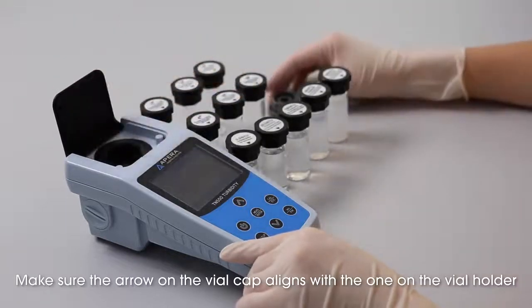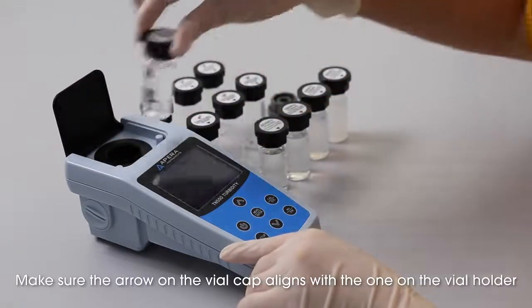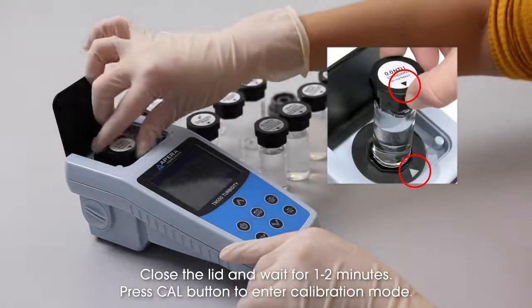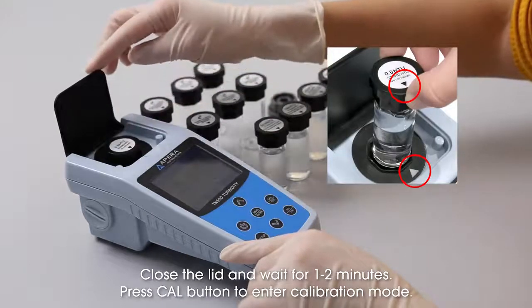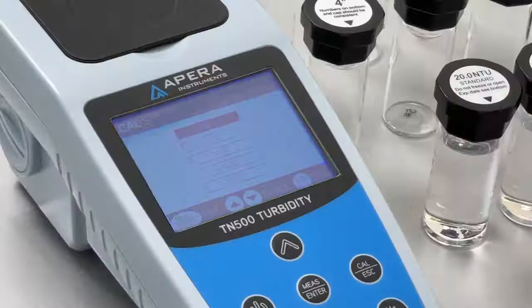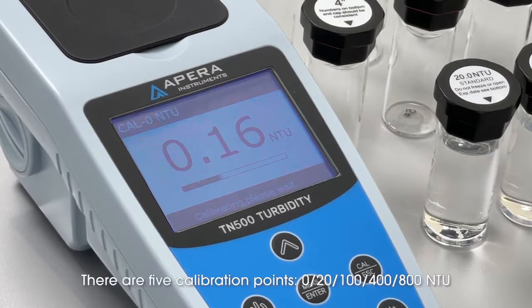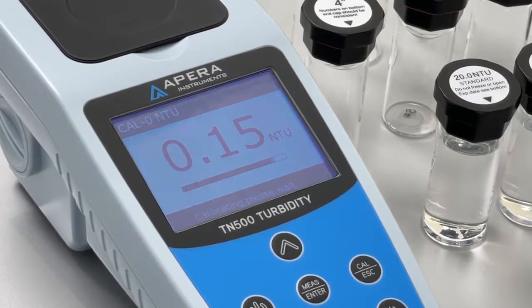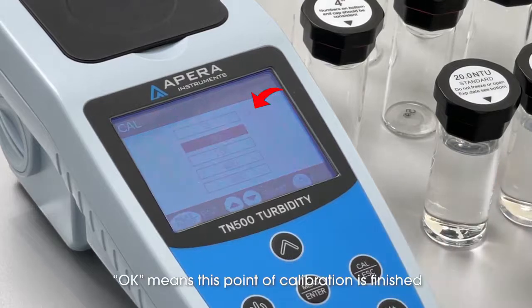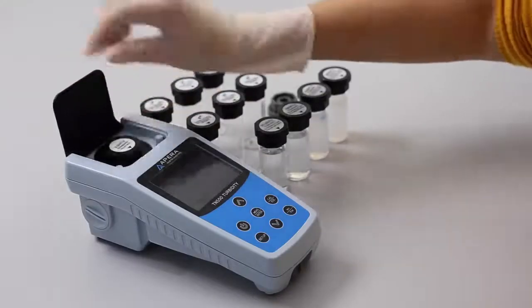Make sure the arrow on the vial cap aligns with the one on the vial holder. Close the lid and wait for 1 to 2 minutes. Press the Cal button to enter calibration mode. There are 5 calibration points: 0, 20, 100, 400, and 800 NTU. OK means this point of calibration is finished.